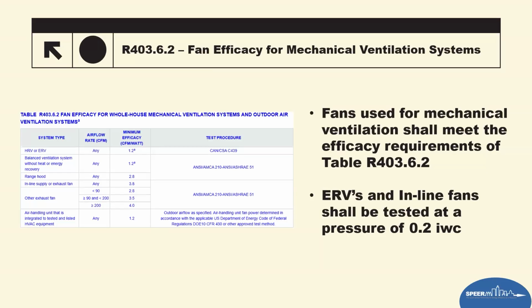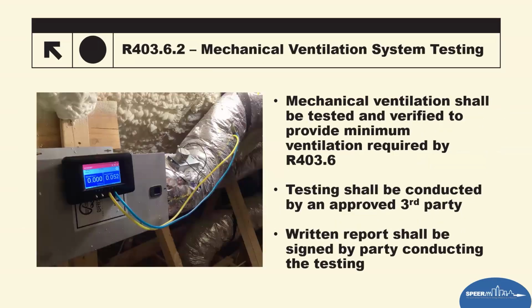And then lastly, all ERVs and HRVs and inline fans must be tested at a pressure of 0.2 inches of water column. So that's just setting the parameters of third-party testing and how it's actually done. Mechanical ventilation testing was added to the 2021. It used to be only an Energy Star requirement, and then code said, well, you have to have mechanical ventilation, but it didn't ask for anything further. In 2021, it now says it must be tested and verified to meet the ventilation requirements for each building.